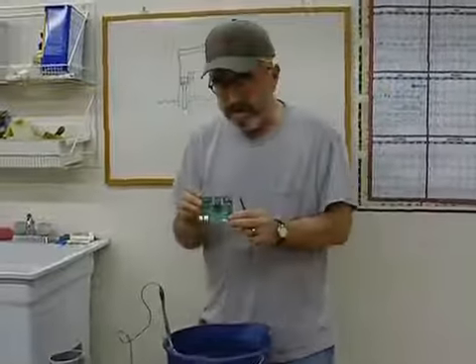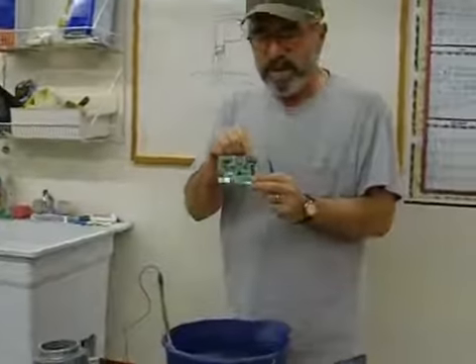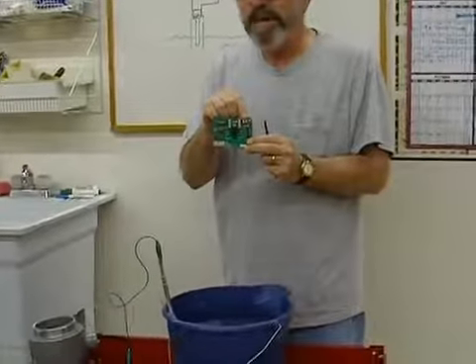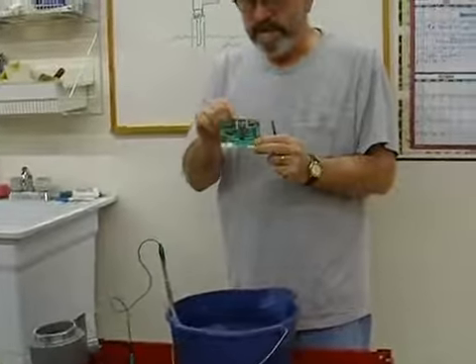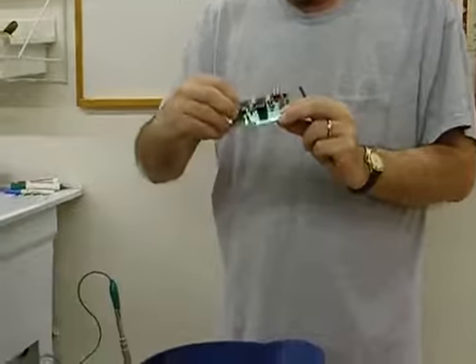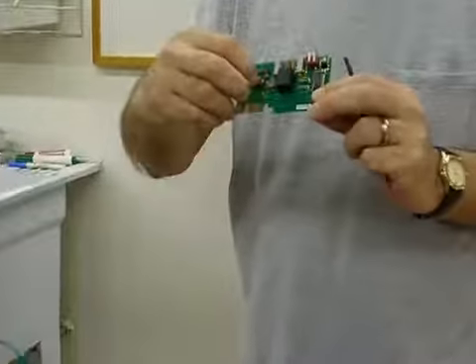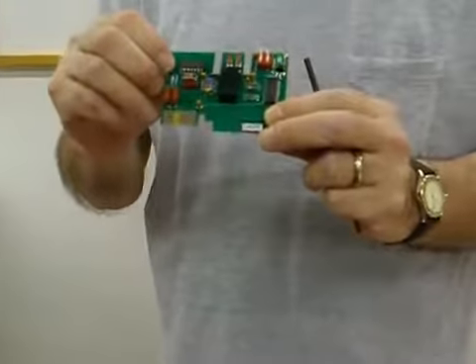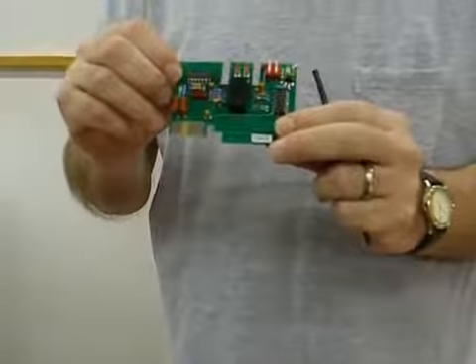This is the dual point card with both of the dip switches set up. This is for automatic fill. This is the low set point, the high set point. There's a slide switch here to set it on low or high sensitivity. I'm setting this one on high because the probe is only 12 inches long.